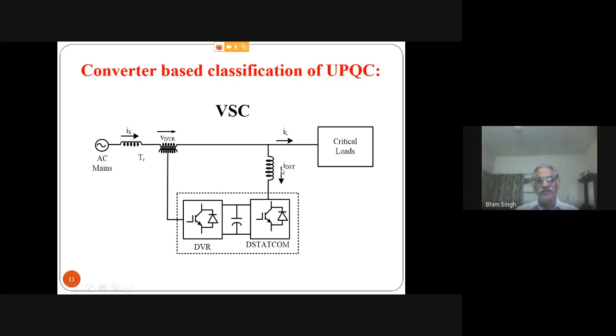But when you go to the current source converter, on the DC link to realize a current source you need an inductor, which is costly, bulky, and noisy—all drawbacks. Apart from that, on the AC side, because the converter will generate PWM current, and you want continuous current here, it means PWM current brings high frequency harmonics, but you need the low frequency currents or reactive current. So to avoid the high frequency current, you need a capacitor, which is not needed as a shunt capacitor in case of the STATCOM voltage source converter.